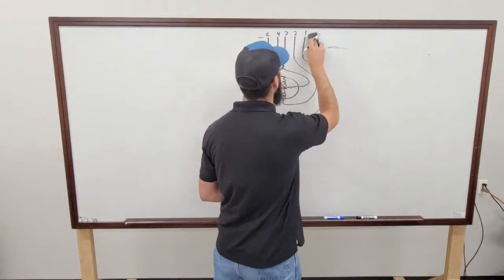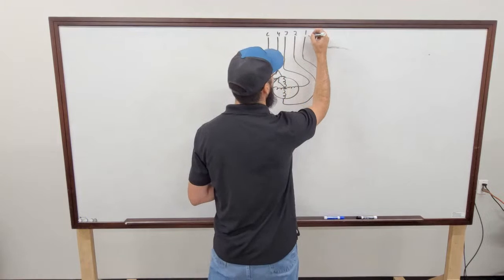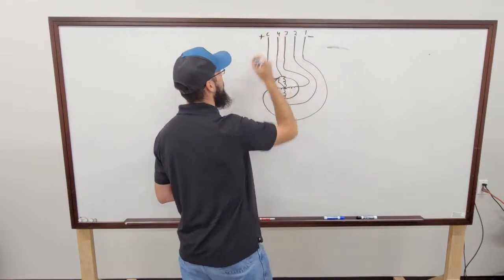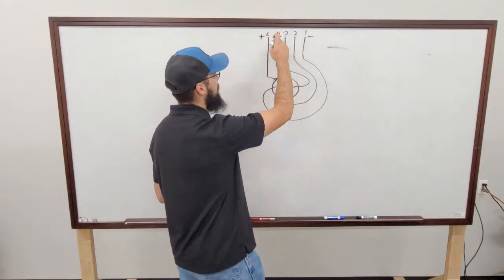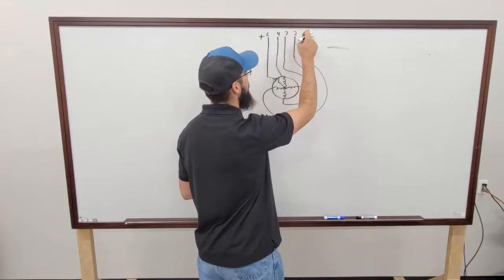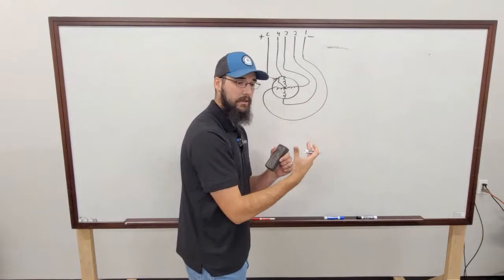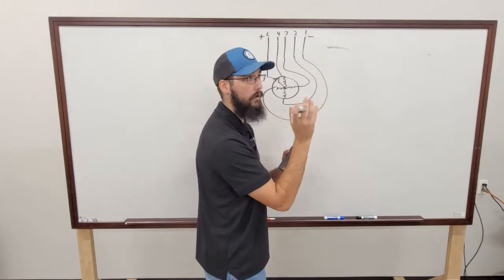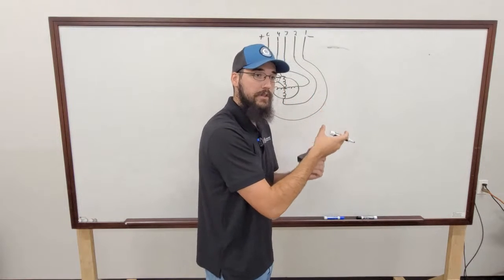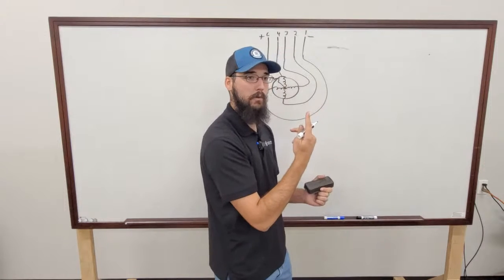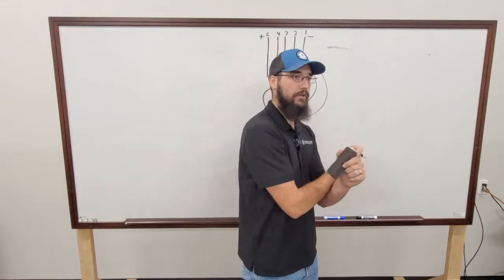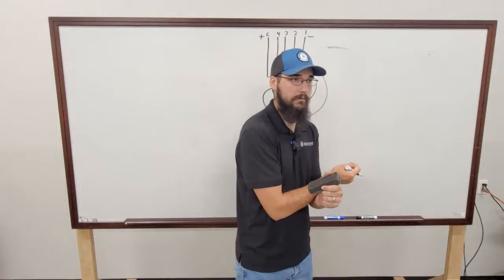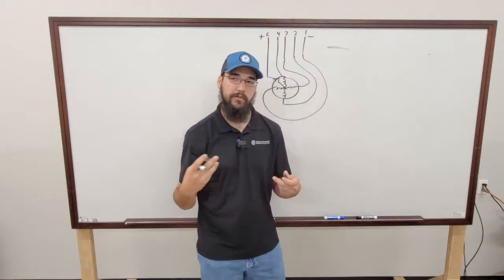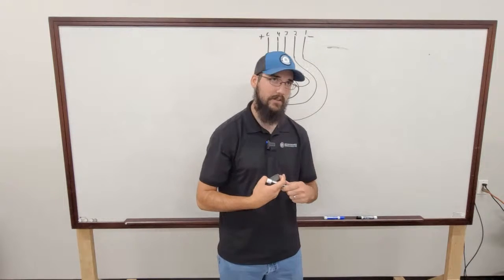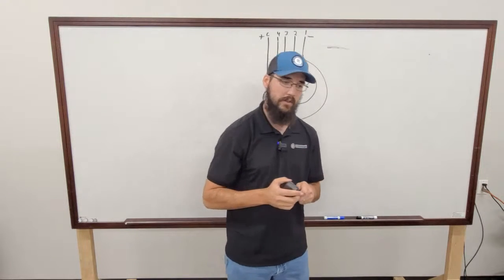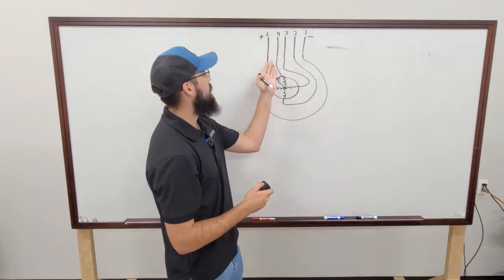Then if we want to open it, the controller is going to flip that around, and this becomes our negative. This becomes our positive signal. And then we step that right back out. 4, 3, 2, 1, 4, 3, 2, 1. By reversing the polarity, we reverse the direction of the current flow, which instead of spinning it clockwise, it now spins counterclockwise, the same way you would have it if you reverse 2 motor leads on a 3-phase blower motor. We're just changing the magnetic field, and this should be all DC current.